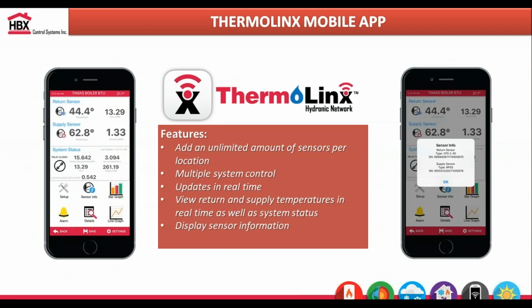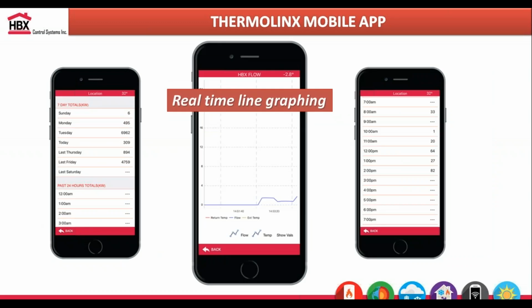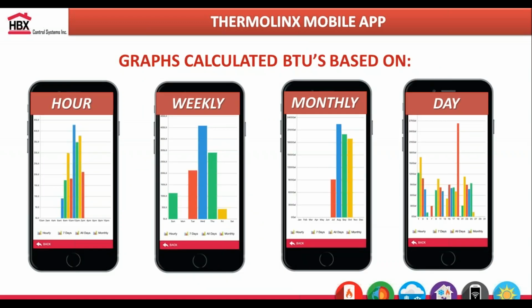Again, the app is free. You can see a lot of information. You can get data in raw numbers or through graphing. You can see your flow, so if you want to balance your hydronic system instead of manually going to each pump, you can just do it through the app and see that real-time line graphing. In terms of using these sensors to monitor just flow or the actual heating BTUs, you can see it daily, weekly, monthly, all through the app.